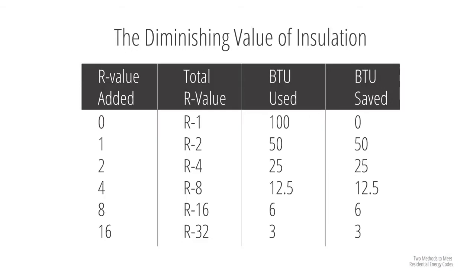To understand this, let's look at a simple example — energy lost through the ceiling. In this example, we start with only a one-inch thick piece of drywall for our ceiling, initially uninsulated. Looking at the first row of the table, we have zero R value added, giving us a total system R value of R1. The BTUs used is 100, and we've saved no energy because we've added no insulation.